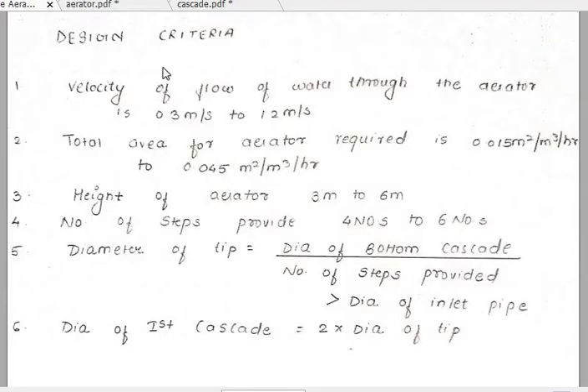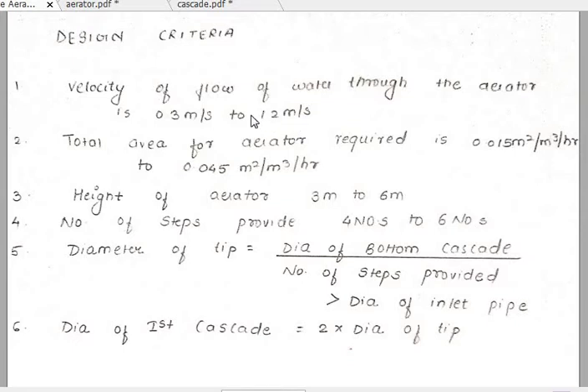These are the six types of design criteria based on which we have to design the cascade aerator, and it is a very important question from the examination point of view. Point number one: the velocity of flow of water through the aerator is 0.3 meter per second to 1.2 meter per second, meaning the velocity should be kept within this range.